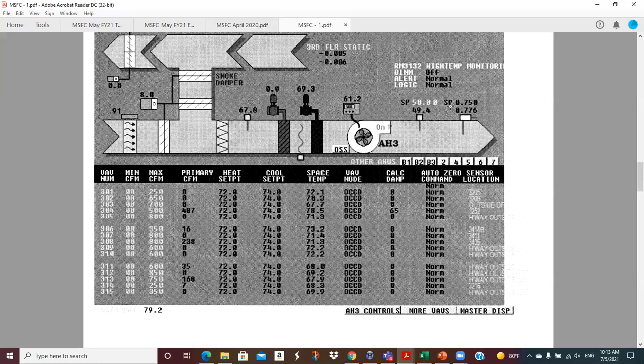And this is static pressure. So this is the pressure in the duct. This is maintained by the VFD, because all these boxes are downstream of this thing opening and shutting. In this case, they're probably shutting if it's this cold with no load in the building.